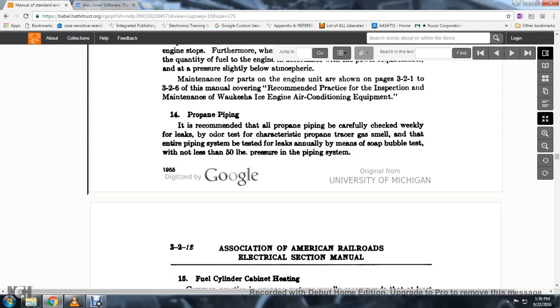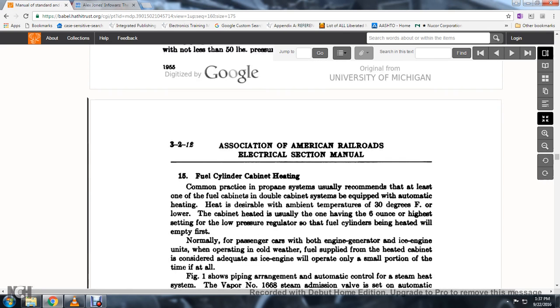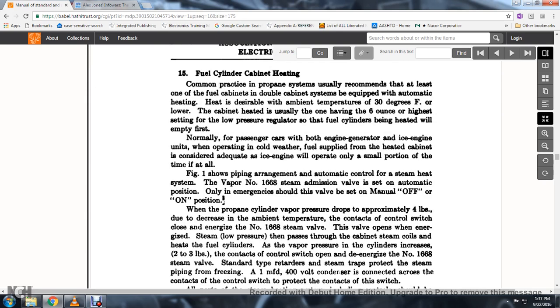14. Propane piping: all propane piping should be carefully checked weekly for leaks by the characteristic propane gas smell. Test the entire piping system for leaks annually by means of a soap bubble test at not less than 50 pounds pressure. 15. Fuel cylinder cabinet heating: common practice in the propane system is to equip at least one of the fuel cabinets in double cabinet systems with automatic heating, maintaining a temperature of 30 degrees Fahrenheit; the cabinet is heated usually with the low pressure regulator set to approximately six ounces.